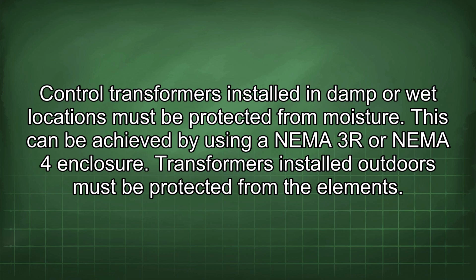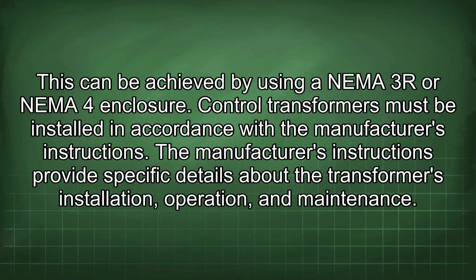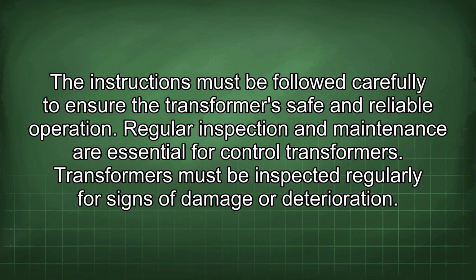Transformers installed outdoors must be protected from the elements. This can be achieved by using a NEMA 3R or NEMA 4 enclosure. Control transformers must be installed in accordance with the manufacturer's instructions. The manufacturer's instructions provide specific details about the transformer's installation, operation, and maintenance. The instructions must be followed carefully to ensure the transformer's safe and reliable operation.